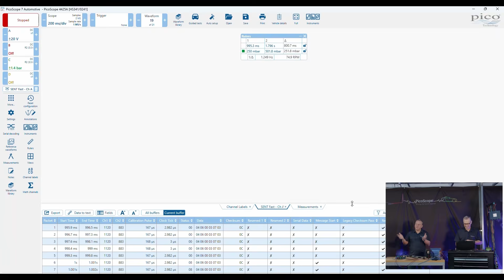I think it's important to stress here, Steve, that at this point, if you were going across the measuring range of the sensor and you graphed it out like that, just by doing that simple check, if you had dropouts, spikes down or up in the data value, you could probably deduce that this sensor is giving you erroneous data. The fact that it's replicated the measured value of the WPS, or the shape of that, probably suggests it's doing okay.